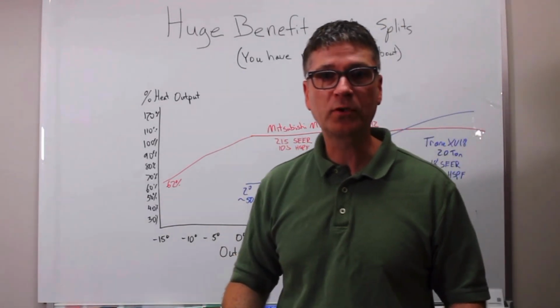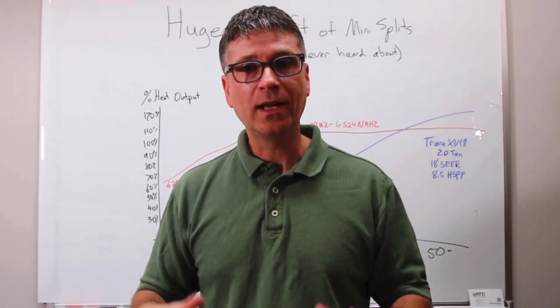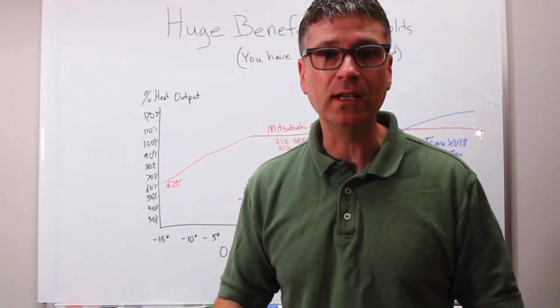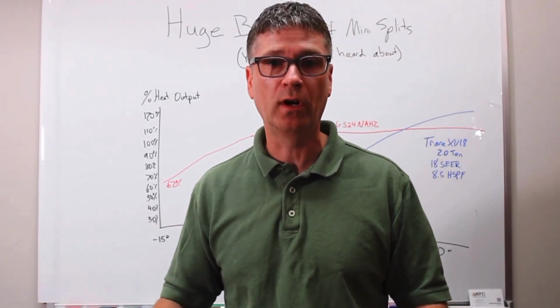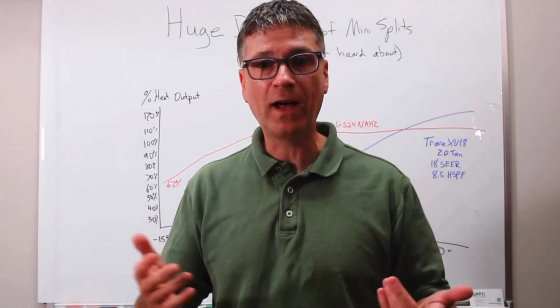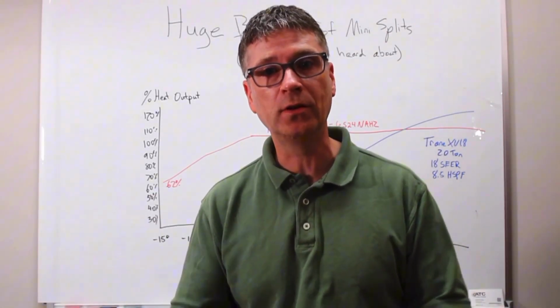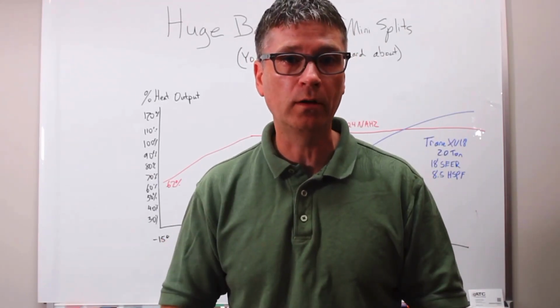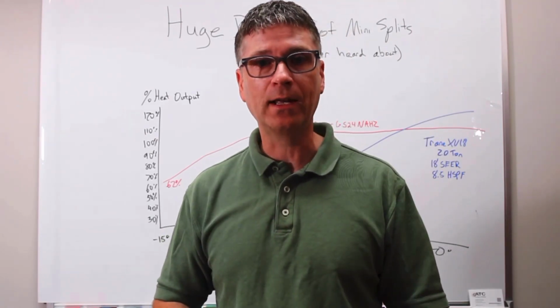When the outside temperature is really low and your heat pump falls in performance, it simply kicks on the emergency heat to make up the difference. Emergency heat is electric resistance heat, and it costs 3 times more to run than the heat pump. In fact, if you were to convert the performance of electric resistance heat to that HSPF number that we just talked about, it would be 3.4. Effective, but really expensive. Now let's look at a mini split.